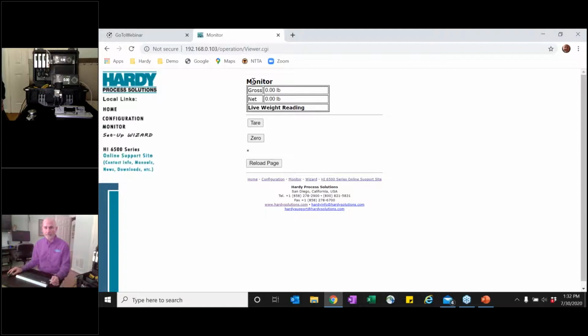Now I'm saying I've got 0 pounds on the scale. This one's reading 0 pounds. This one actually still reads the 0.35, which is the accurate. So I'm going to put this weight on here just because whenever I plug this fan in, you'll see that it's going to bounce around. It'll probably turn and it'll eventually get settled. Hopefully it doesn't fall off, but we'll take a look at it here.